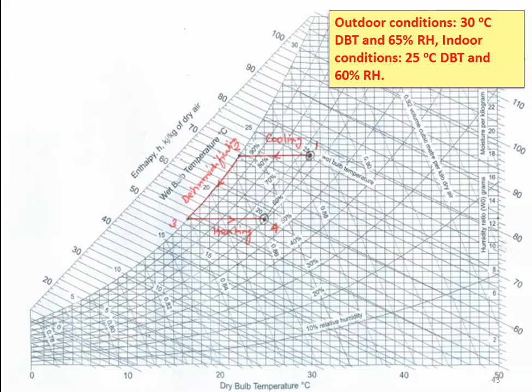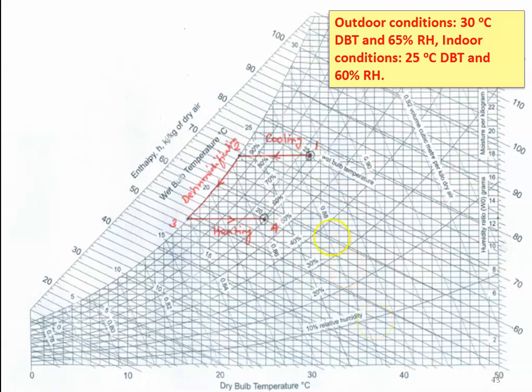We solve using the psychrometric chart. The outdoor conditions are 30°C dry bulb temperature and 65% relative humidity — this is point 1, which lies between the 60% and 70% relative humidity lines. The indoor conditions — the required conditions — are 25°C dry bulb temperature and 60% relative humidity, this is point 4. The process is reducing temperature and decreasing water vapor content: cooling and dehumidification.